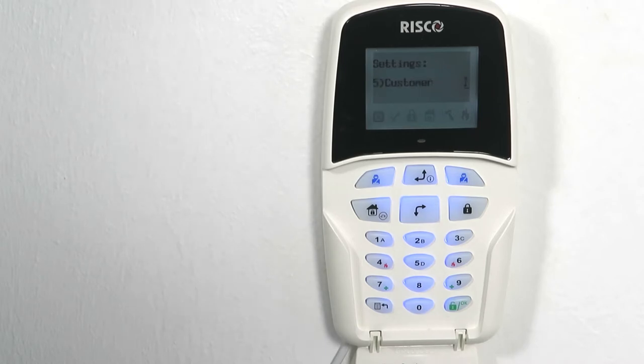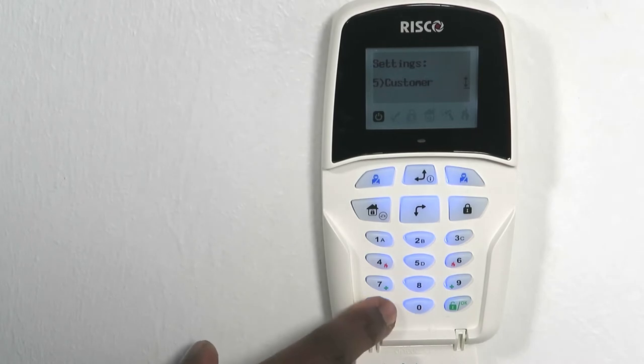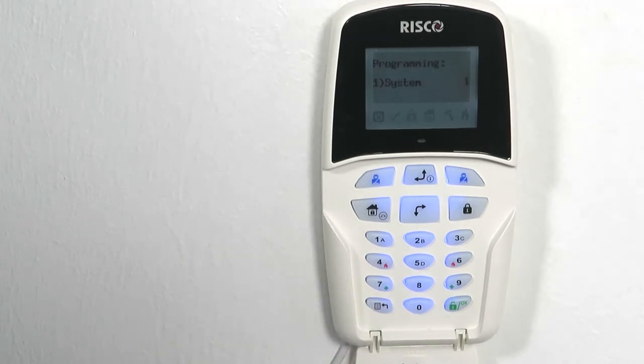To go back to the main programming menu, press the menu button 2 times. Note that this defaults the panel. This action and everything from here on can only be done on the keypad, as the configuration software is not yet capable of handling this customer profile. The default installer code will now be 1561.